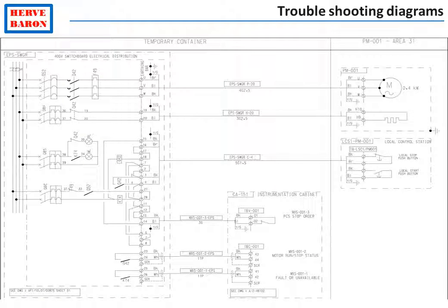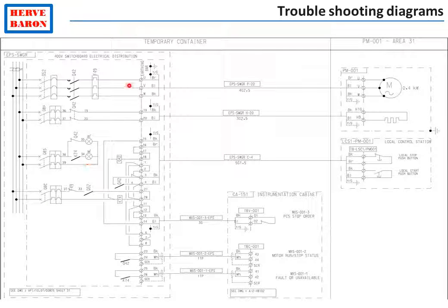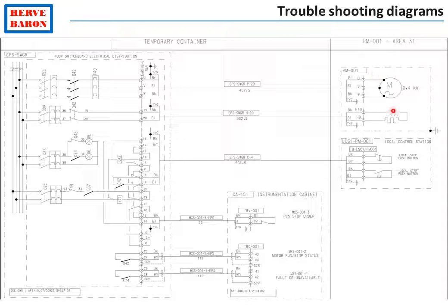Similarly to the instrumentation loop diagram which shows all information related to one instrument, the electrical troubleshooting diagram shows all information related to each consumer — including the reference of the switchboard and cubicle, numbering of terminals, tags of cables, and connections with other systems such as the process control system and emergency shutdown system. This drawing is used for troubleshooting: if there is any issue with a particular power consumer, this drawing shows exactly where to check.